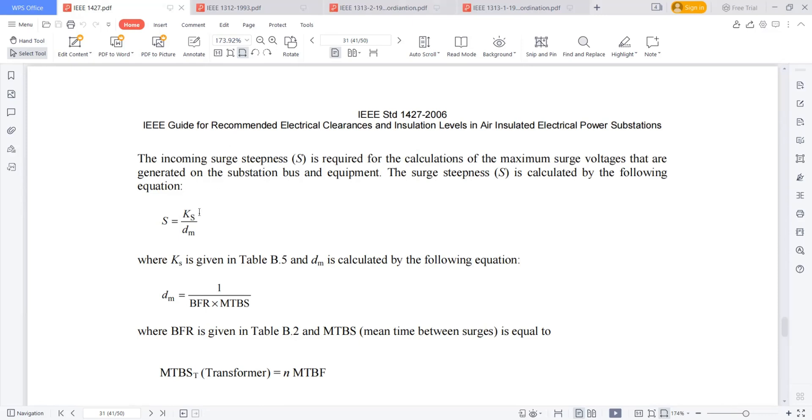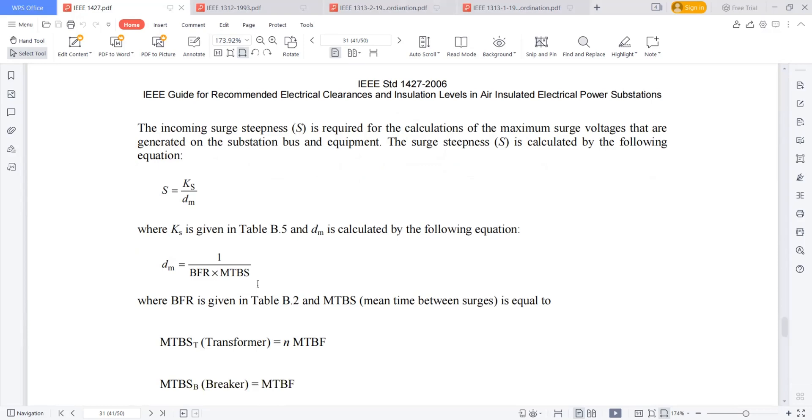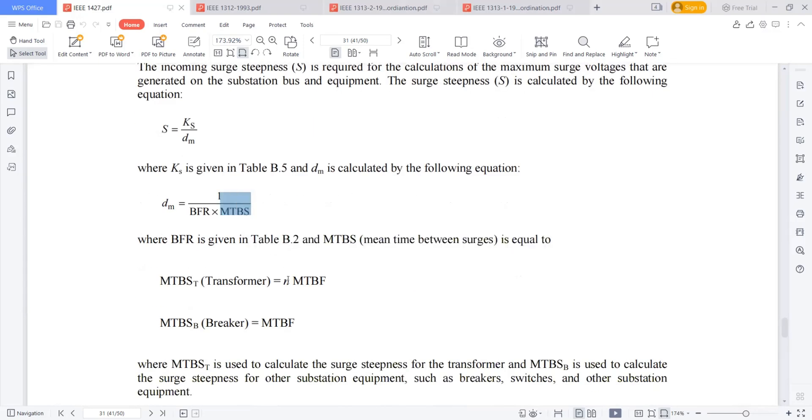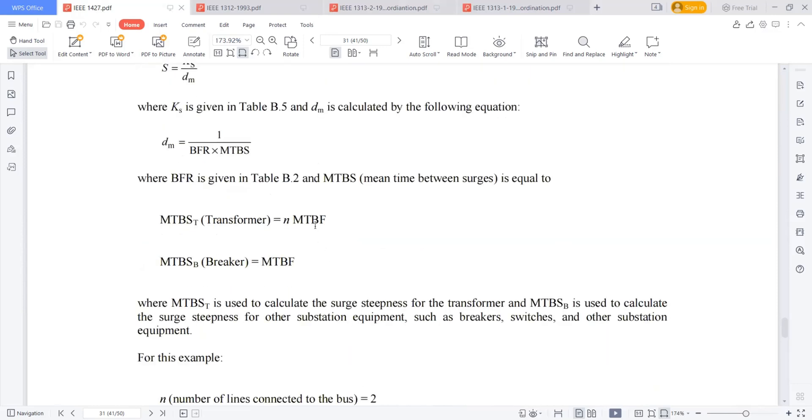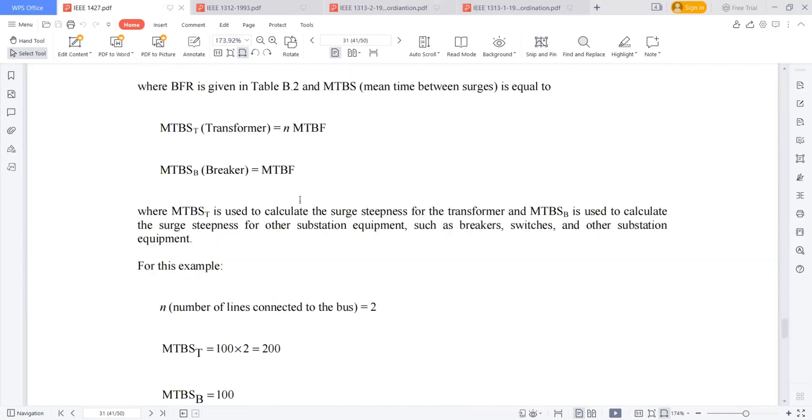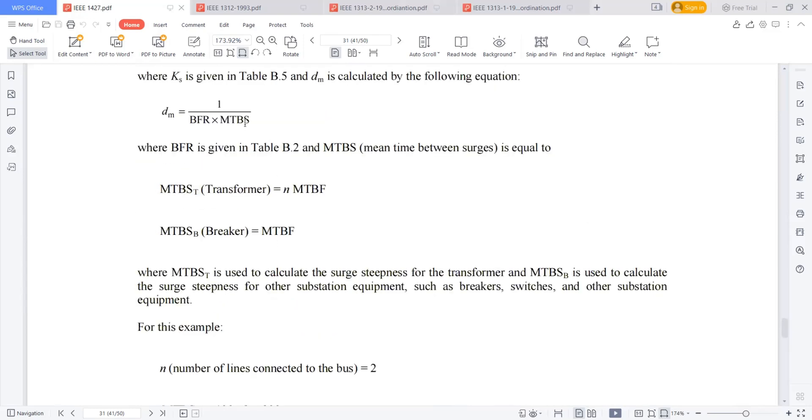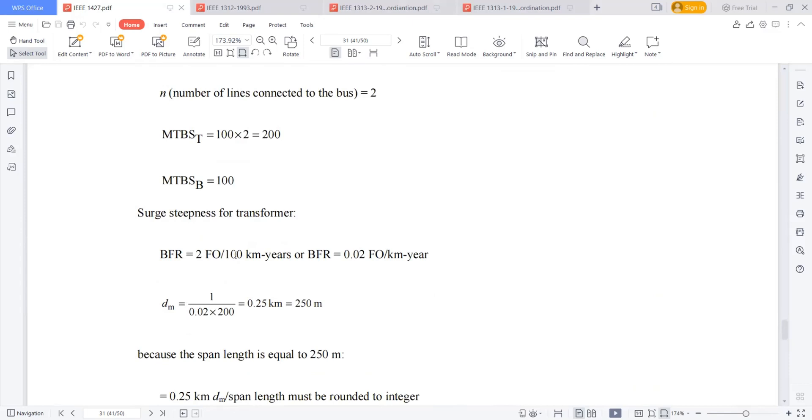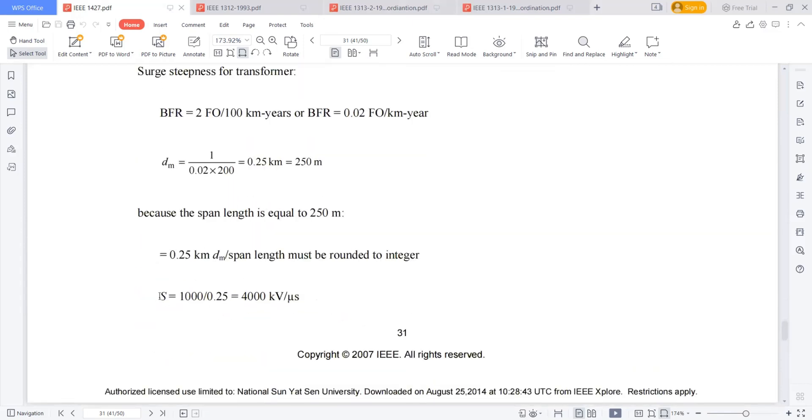How to calculate the incoming surge steepness? Incoming surge steepness is equal to KS, which is some constant, by DM. DM again depends on BFR, back flash rate, and MTBS, mean time between the surges. Where the mean time between the surges depends upon N into MTBF, mean time between the failures of the equipment. If two lines are connected, N equal to two. So I calculated the MTBS and I calculated the DM and I calculated the back flash rate. And from this, I found the surge steepness is 4,000 kV per microsecond.